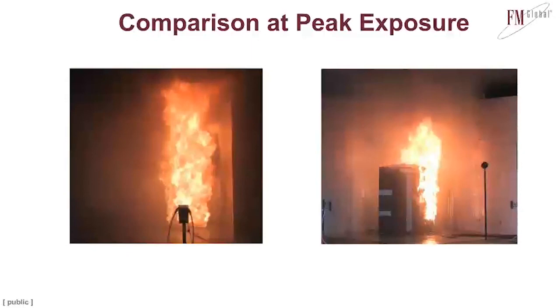So now I wanted to show you a little comparison point between the NMC test and the iron phosphate test. I showed you the NMC test because it's a bigger system and a more hazardous chemistry, so it makes for, I think, a more interesting video. But it is really important to have the counterpoint here to show what other chemistries can do. So here we have on the left the NMC system, and on the right the iron phosphate system. You can see the NMC fire is up to the ceiling, spreading out towards the wall, whereas with the LFP system, the fire is not as tall, it's closer to the rack, and it stays much smaller. I'll show you data on this one in a second.